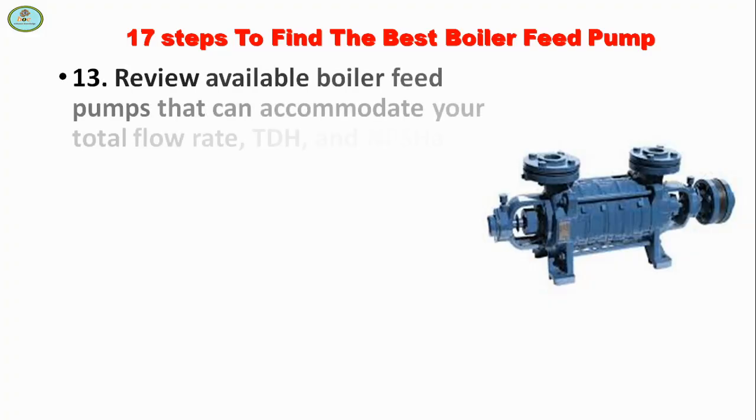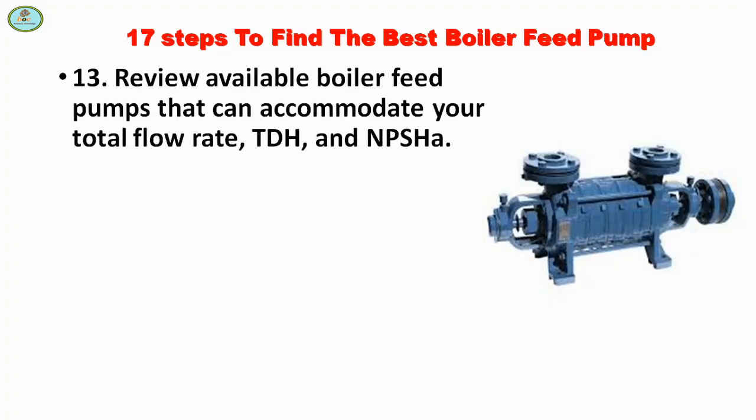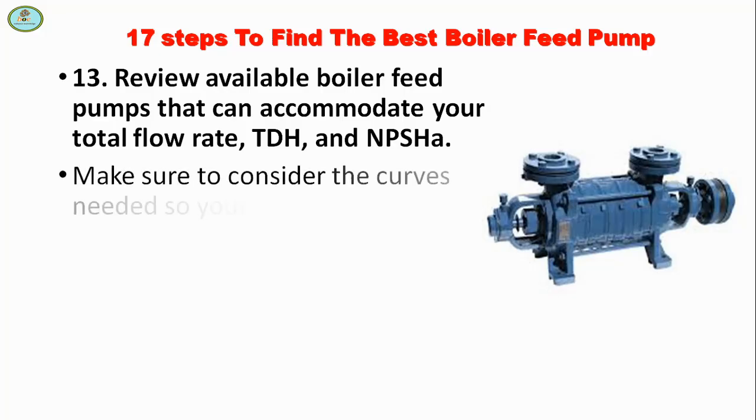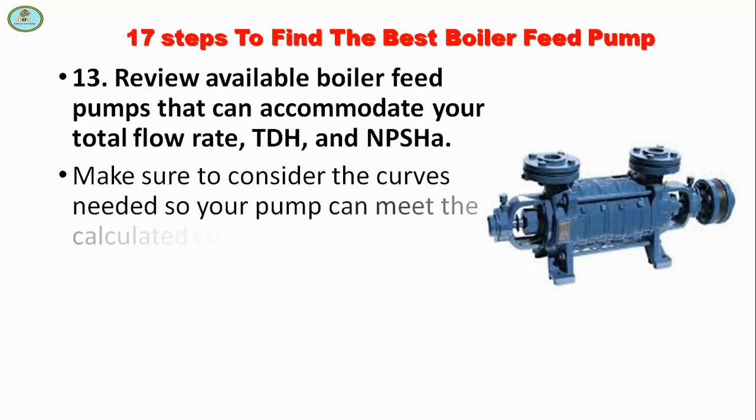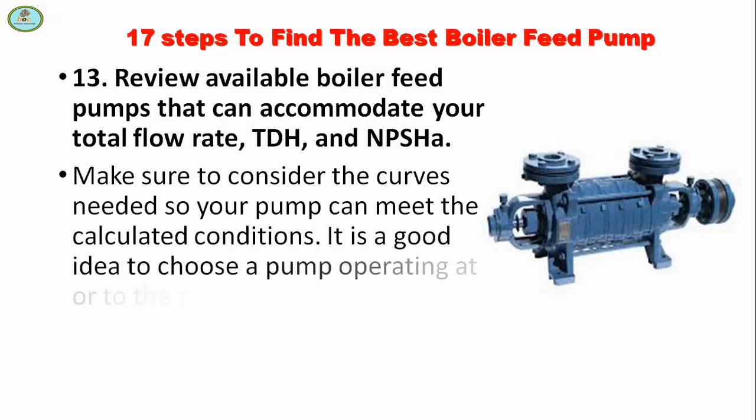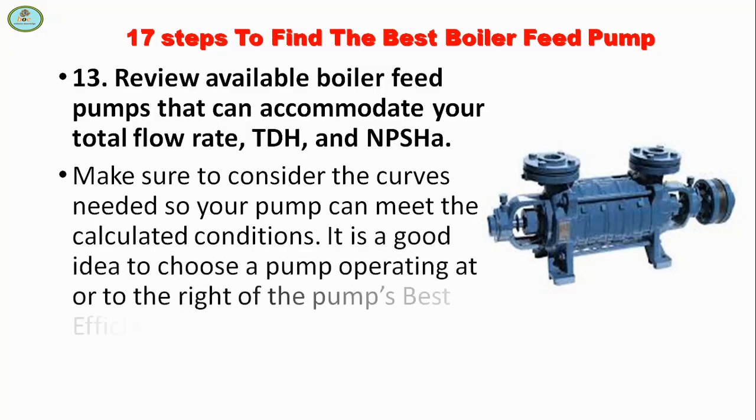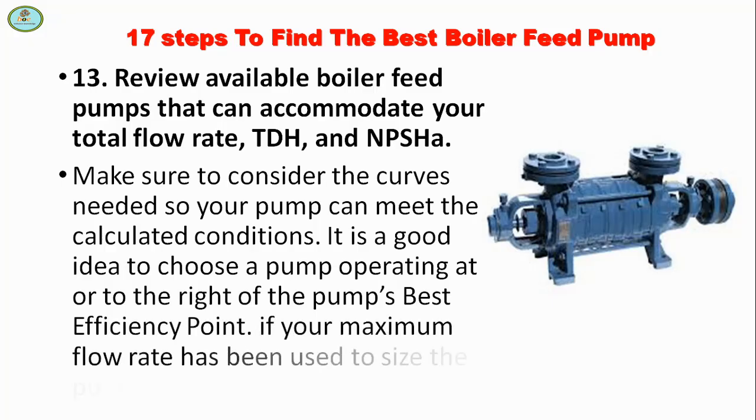Next is to review available boiler feed pumps that can accommodate your total flow rate, TDH and NPSHA. Make sure to consider the curves needed so your pump can meet the calculated conditions. It is a good idea to choose a pump operating at or to the right of the pump's best efficiency point, if the maximum flow rate has been used to size the pump.